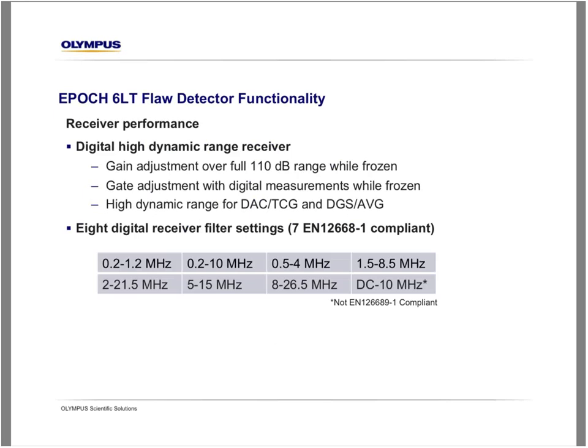From a receiver performance capability, this is also a flaw detector that's built in the full standards of the EPOCH series and the Olympus quality. So we see not only an industry standard gain adjustment up to 110 dB, but also extremely stable signals across that entire range. Very good signal to noise ratio as a result of our very capable digital filtering capabilities. And you'll see here that we have 8 different narrowband filters, and in some cases more broadband filters, to accommodate a very wide range of frequency requirements for flaw detector applications.